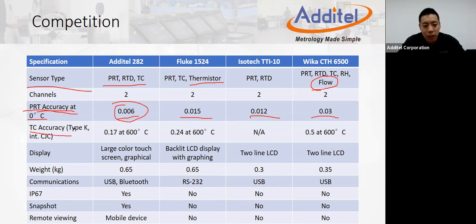Thermocouple accuracy, the example here is using type K and also using the internal cold-junction compensation. We have 0.17 degrees C at the 600 degree C range. The others have 0.24 or 0.5. So for accuracy in thermocouple measurement, we're on top.